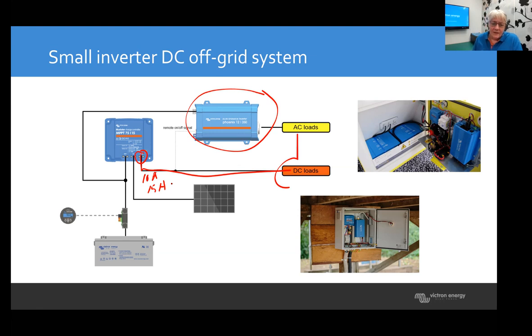So it can't be connected directly to that load output, but what you can do is connect the positive side of the load output to the H terminal of the inverter charger. When the load output is on, it makes that positive output 12 volt. The H terminal inside the inverter sees there is 12 volt there, and that's a sign to turn on. That's a nice way of steering your inverter off the load output without connecting it directly, only the control. You can also put in a battery monitor, which has a relay as well that could potentially turn the inverter on. So there's definitely multiple ways to skin a cat, as the saying goes.